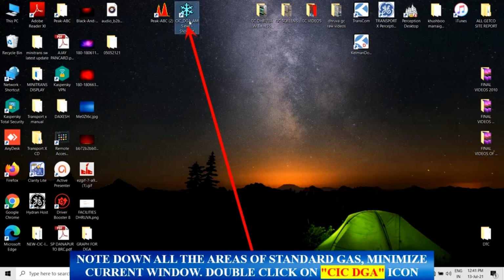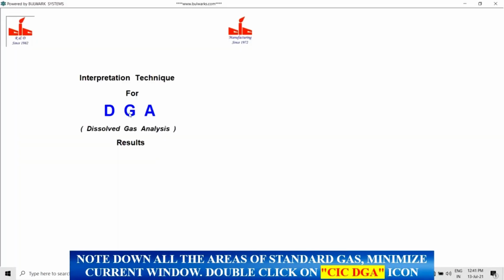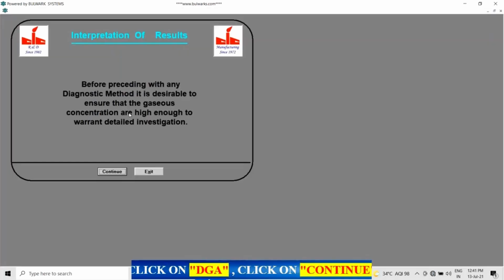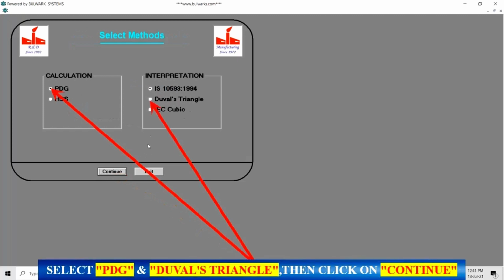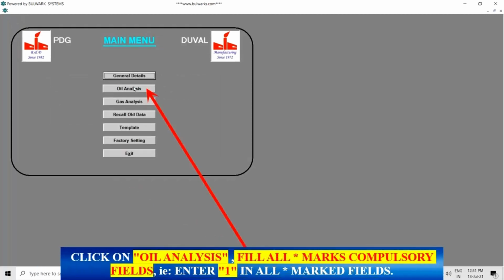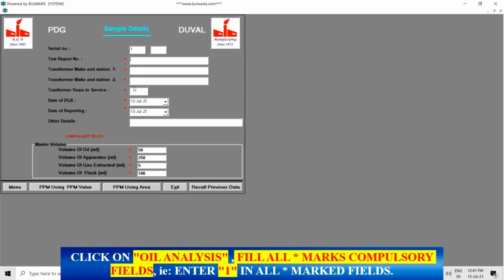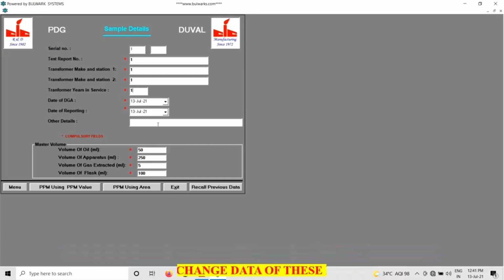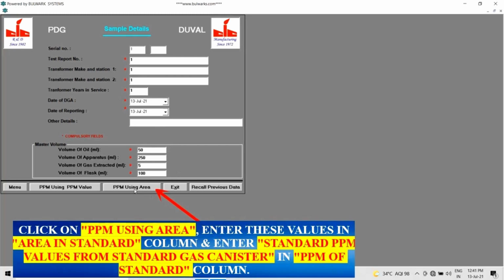Double-click on the CIC DGA icon to open the interpretation software, click on DGA, click on Continue. Select PDG and Duval's triangle, then click on Continue. Click on Oil Analysis, fill all asterisk marked compulsory fields, for example, enter 1 in all asterisk marked fields. Don't change data of these fields. Click on ppm using area.